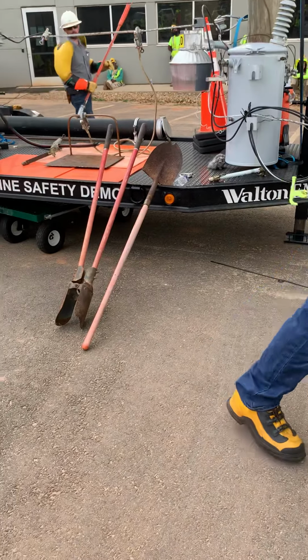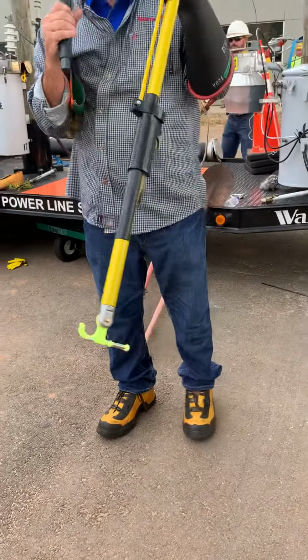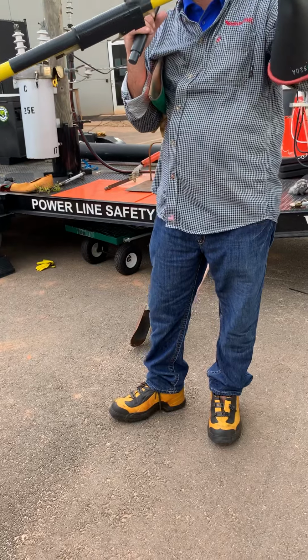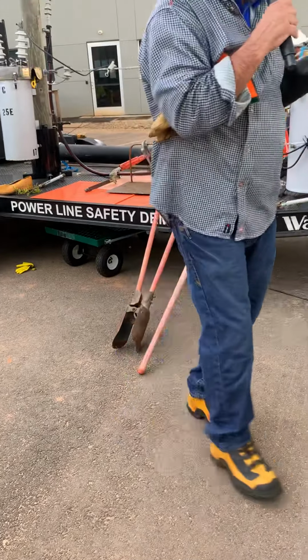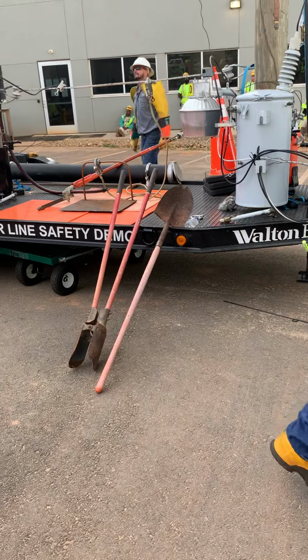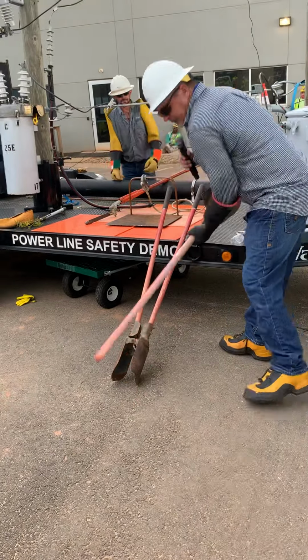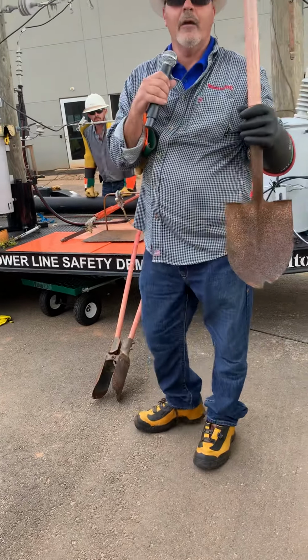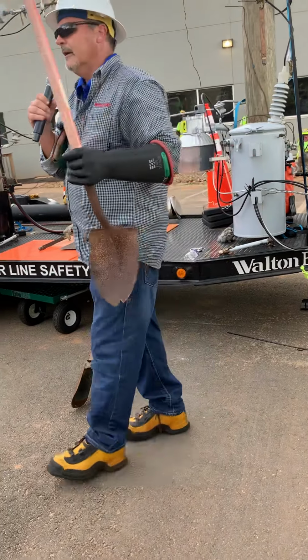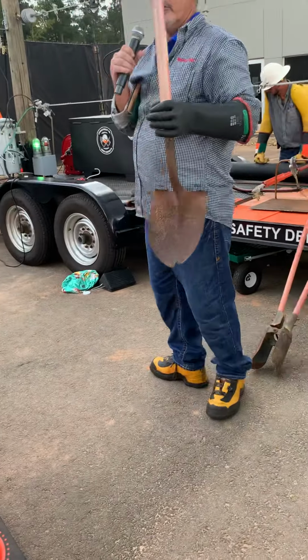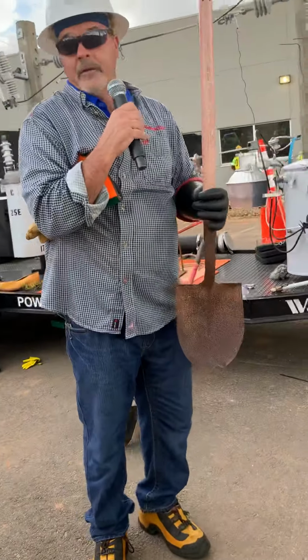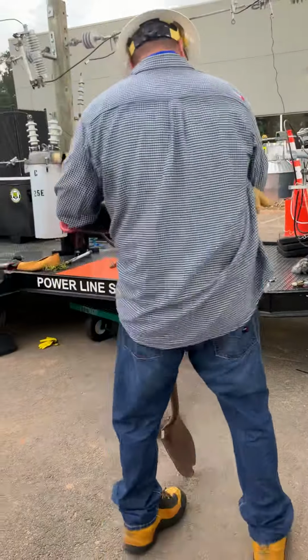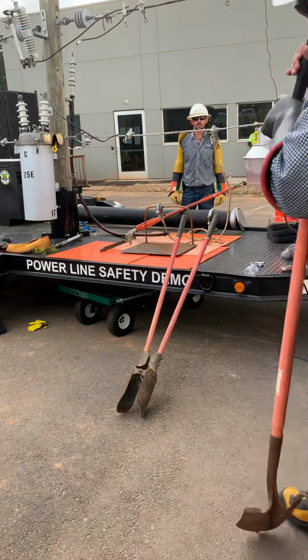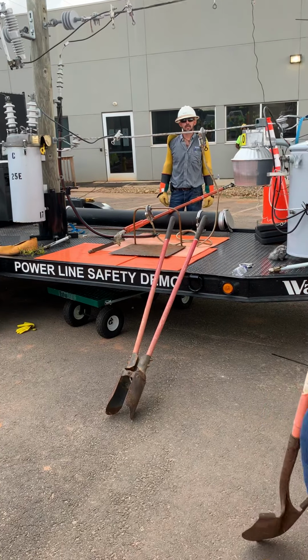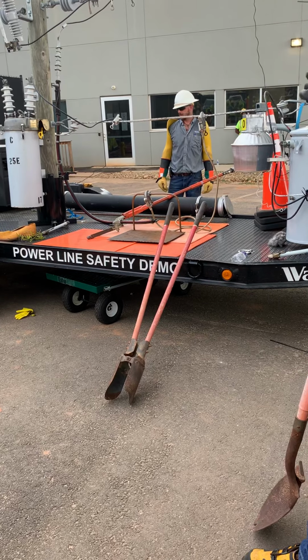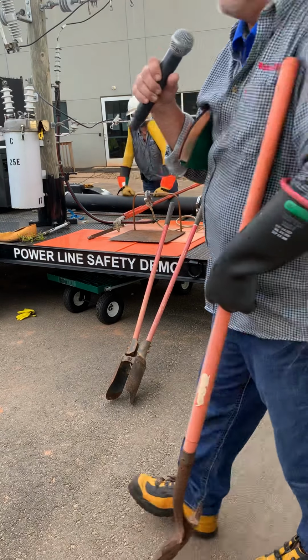The difference is everything we use is tested. These sticks are tested every 2 years, 100,000 volts per foot. That's an OSHA mandate. You can look at this shovel handle. It's faded out. It's got wear on it and could have oil, grease, dirt, and it's not tested. So you got no idea whether it's conductive or non-conductive. All right, I got to get my glove back on, but when I do, guys, when I touch this shovel against the primary underground there, it's gonna blow a fuse. So you might want to stick your fingers in your ears.